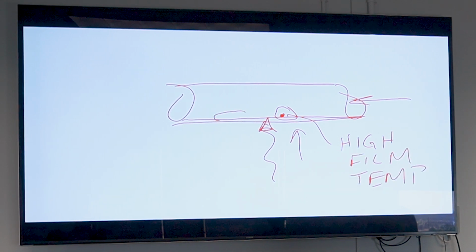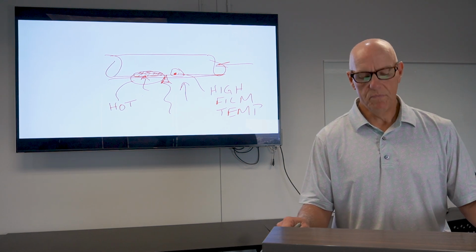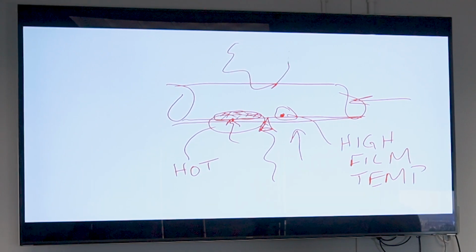And then I can lay down carbon, I'll lay down a deposition of carbon. Now this heat transfer that's trying to go in there is blocked, because that carbon becomes insulating. And when it insulates, this portion of the tube right here gets really hot, too hot. If it gets too hot, it fails, and I've got a failed coil. So it's really not about flame hitting a tube.